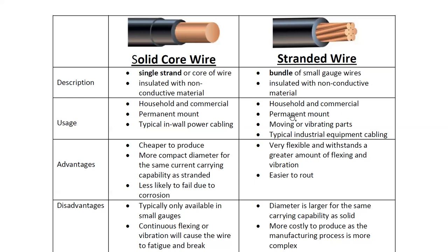Here's the main difference, household versus... Can you install stranded wire in a household situation? Yes, you can, but normally it's not done because the stranded cable is way more expensive. So that's probably the biggest reason. And it's easier to install the solid core, and mostly we're going to use the screw terminals for our purpose. Sometimes you do the WAGO or the Marette type of connectors, which we'll talk about in further lectures.